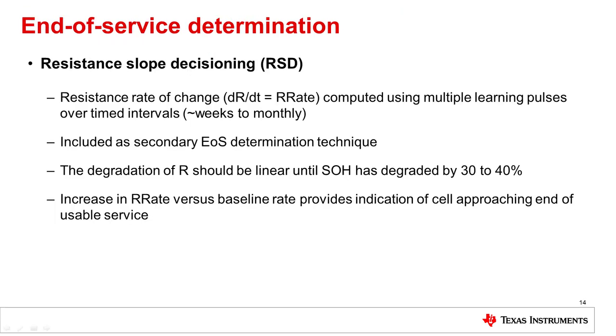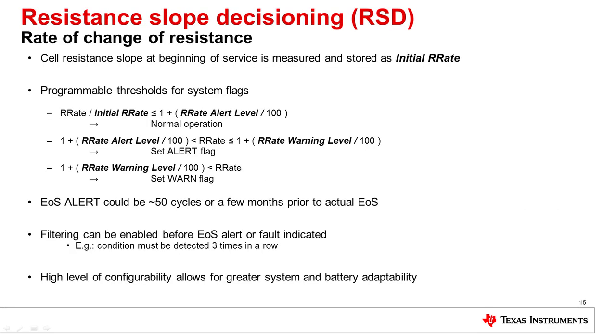The second approach to analyzing R cell values is Resistance Slope Decisioning, or RSD. This technique looks at the slope of R cell changes versus time. It takes multiple R cell readings, and as the slope increases it expects a somewhat low or linear slope in the early stages of aging. As more significant aging occurs, the slope increases and you can trigger alerts and warnings to the user that the cell needs replacement. Rather than looking at R cell values directly, RSD looks at the R rate — the derivative of R cell versus time — and makes decisions based on that.